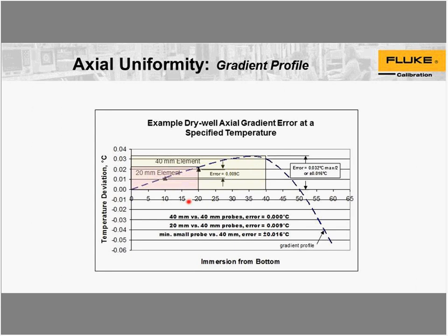An examination of that. Look at what if we were comparing probes, all the same sensor length, all the same general construction. What actual temperature might be some integrated value over that sensor length that would be here, and if you were to measure all of them the same size, it would be pretty similar. If we compare a thermometer of a different dimension, now we've got, on here, I just drew what it might look like for a 20 millimeter element.